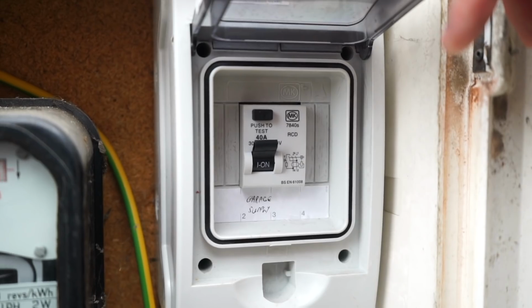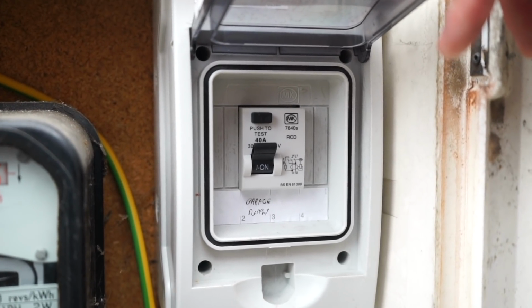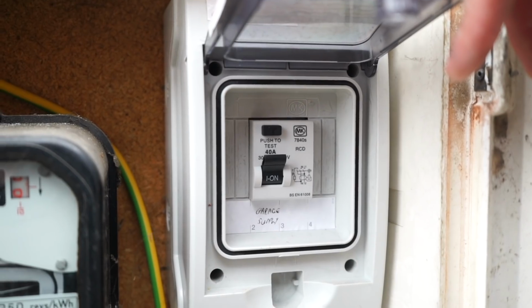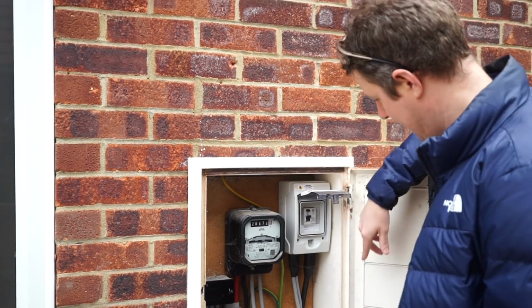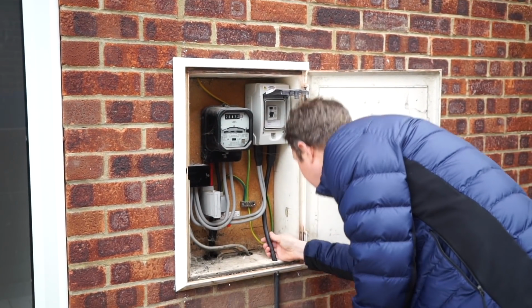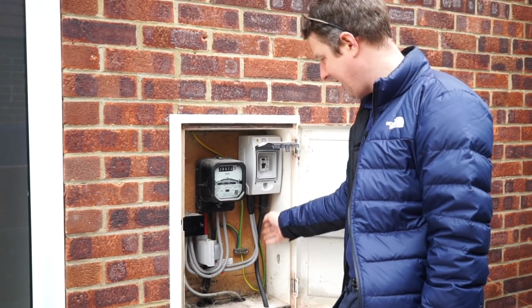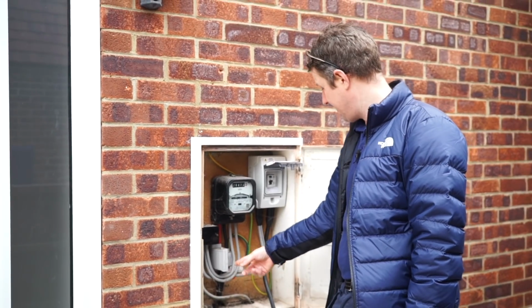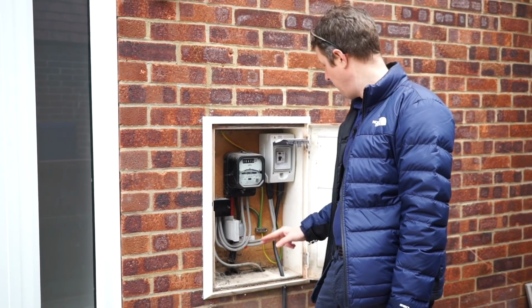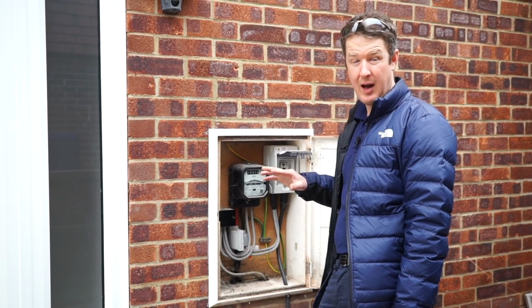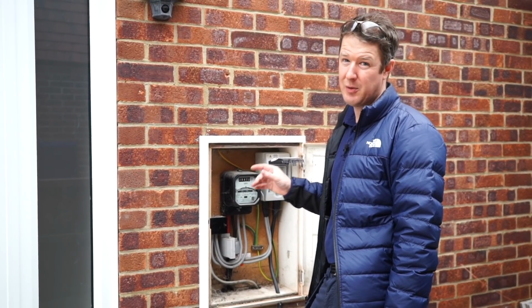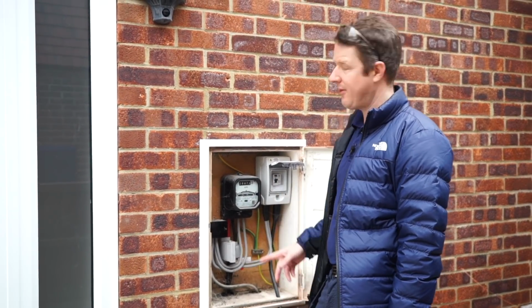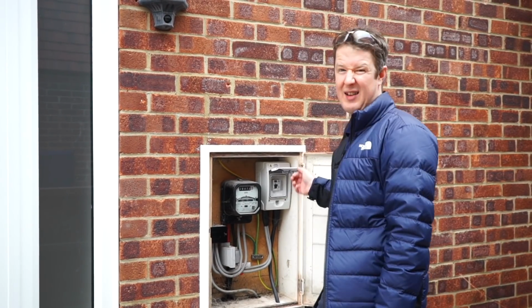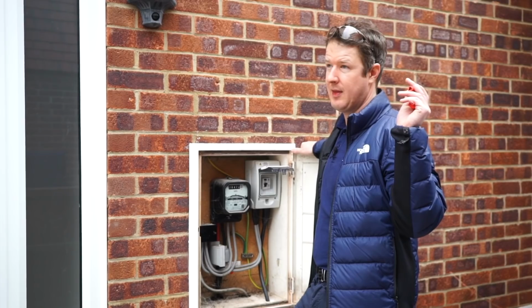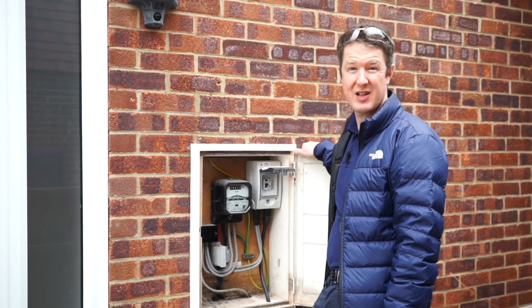So if you notice, it's got a BSEN number, it's a 61008. That means it's an RCD, not an RCBO, which means it has earth leakage protection, but not overcurrent protection. So this cable, which is probably a 6mm armoured or something, is only being protected by the 100 amp main fuse, which means if something goes wrong, dead short between live and neutral, the RCD is not going to trip because there's still a perfectly balanced current between live and neutral, but it's going to blow the main fuse. So whoever fitted that, which looks like it was done in 2015, the customer said that the previous owner actually turned the garage into a studio.